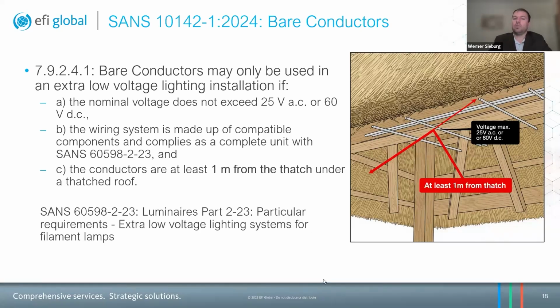The problem I have with this requirement in the context of a lodge, for example, is that your lighting needs to be somewhat higher than what a person can reach, and also needs to be high enough to illuminate the room. And the bare conductors are very often strung between the two walls of the room. Now, if the thatch actually gets to very near to the position where the bare conductor is being strung from, that requirement can no longer be met. And so I just thought to point that out. There is obviously a reason why this requirement was brought in. And the designers will need to be very creative in terms of how to adhere to this requirement while also making the place appealing.